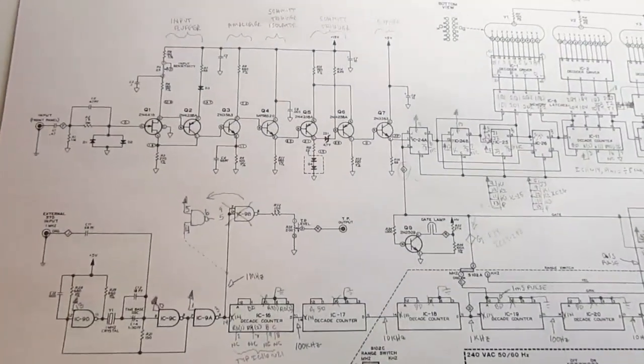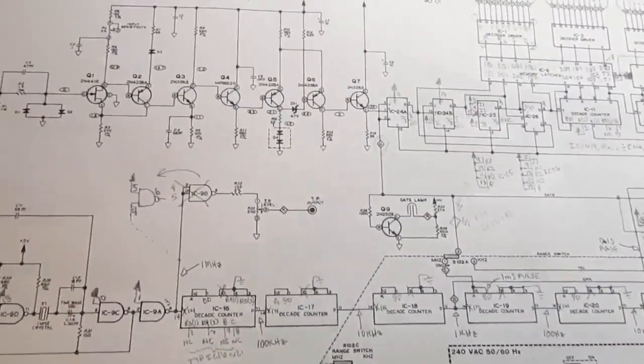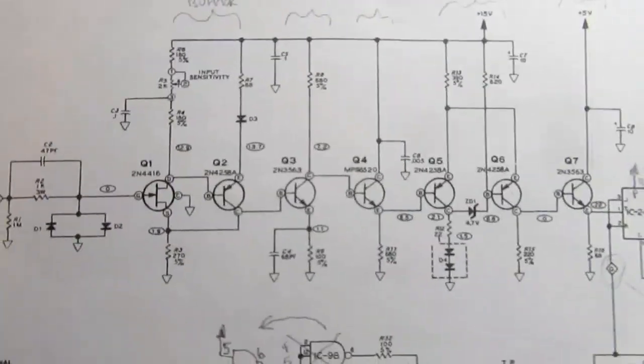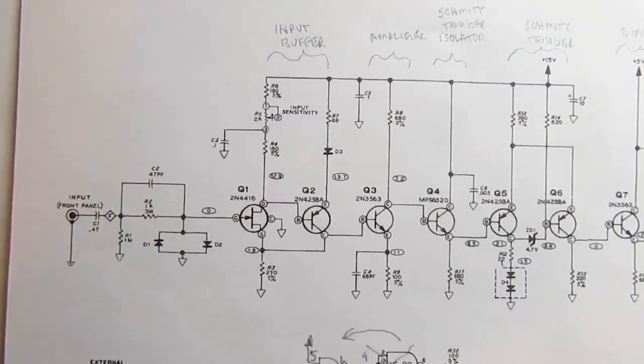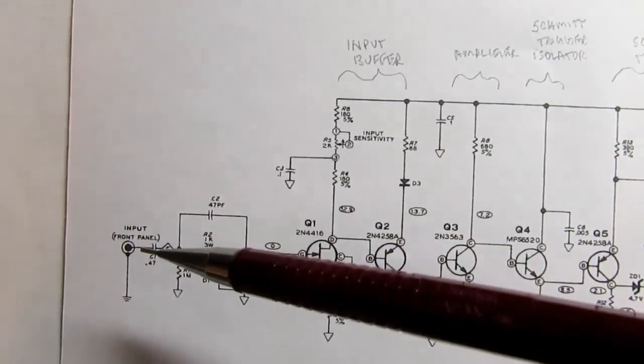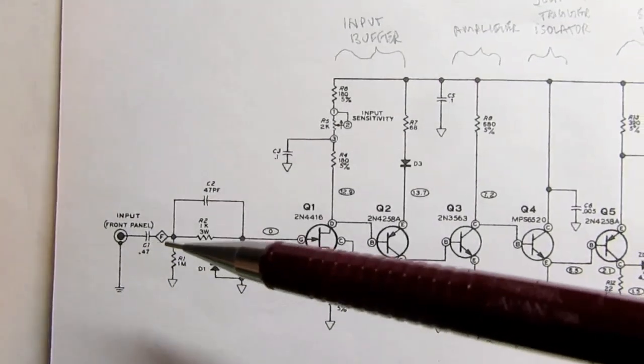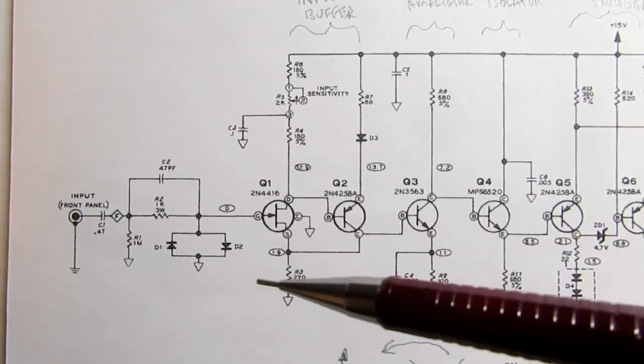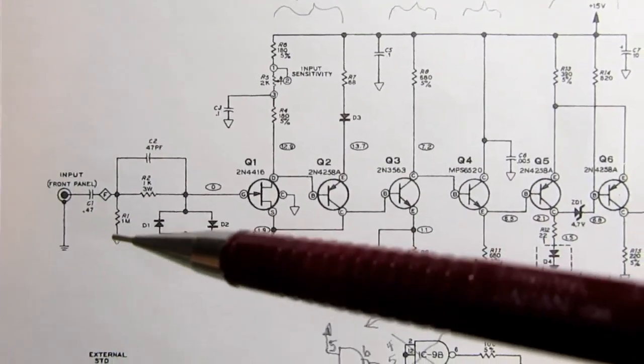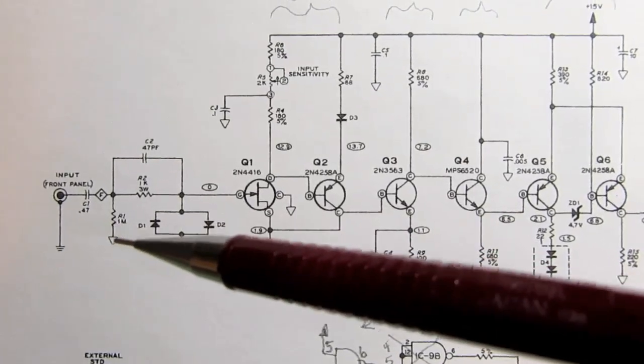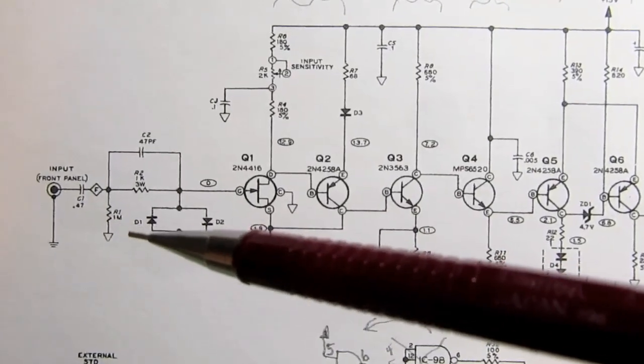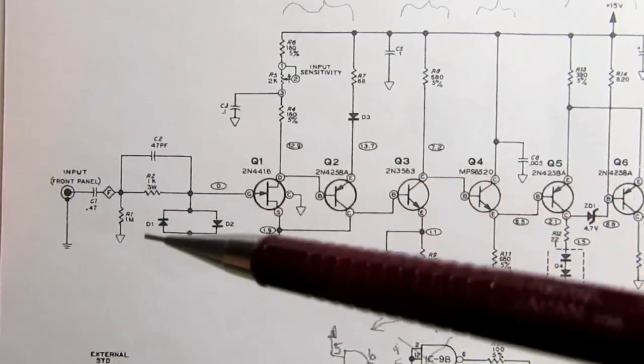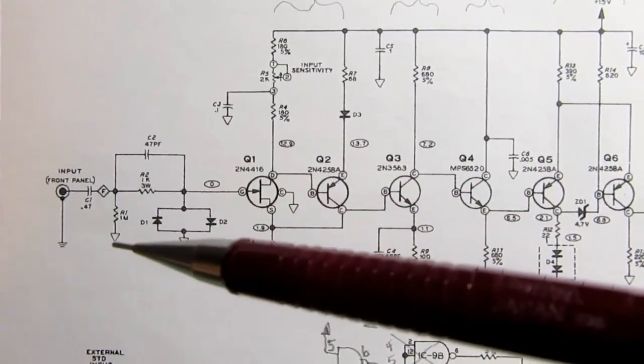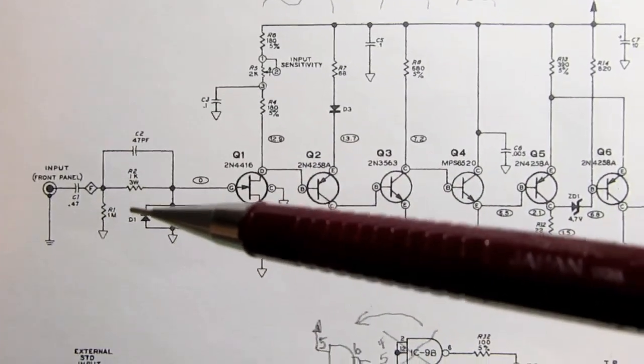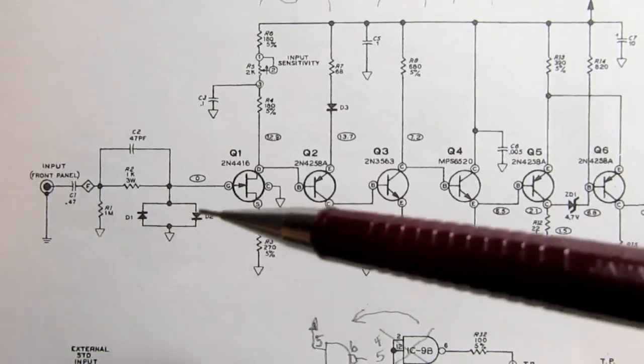Well, the next thing we need to do is condition the input. This frequency counter has a wide range of inputs it can accept. In certain frequency ranges, it can accept inputs of a couple hundred volts. As the frequency goes up, it has to be a lower and lower voltage, until, if you're up around its maximum frequency, it can only be a couple volts.